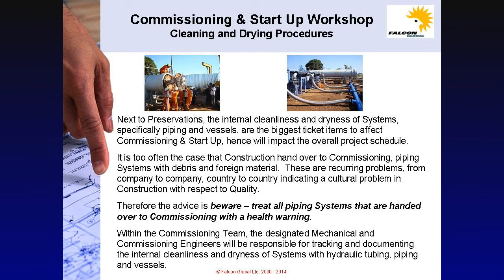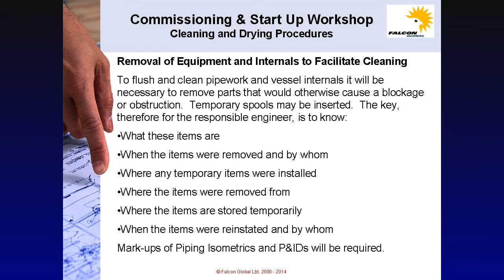Within the commissioning team, the designated mechanical and commissioning engineers will be responsible for tracking and documenting the internal cleanliness and dryness of systems with hydraulic tubing, piping and vessels. In order to flush and clean pipework and vessel internals, it will be necessary to remove parts that would otherwise cause a blockage or obstruction. Temporary spools may need to be inserted.